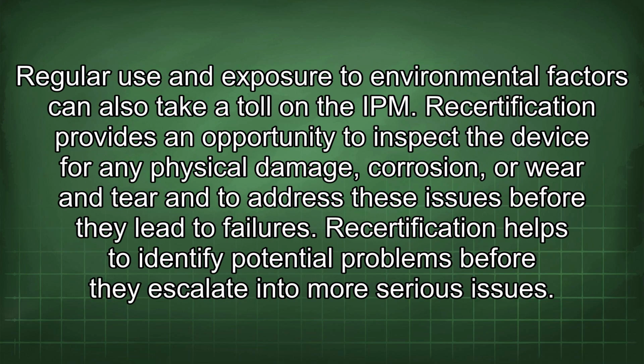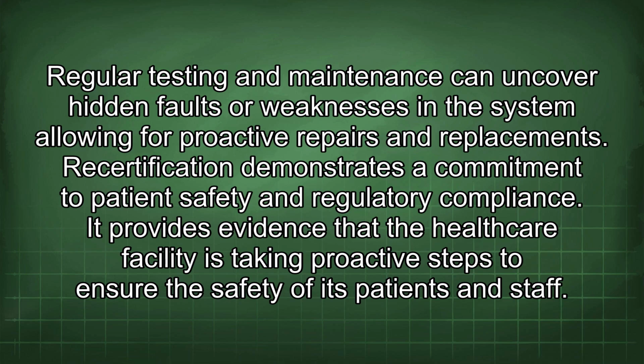Regular use and exposure to environmental factors can also take a toll on the IPM. Recertification provides an opportunity to inspect the device for any physical damage, corrosion, or wear and tear, and to address these issues before they lead to failures. Recertification helps to identify potential problems before they escalate into more serious issues. Regular testing and maintenance can uncover hidden faults or weaknesses in the system, allowing for proactive repairs and replacements.